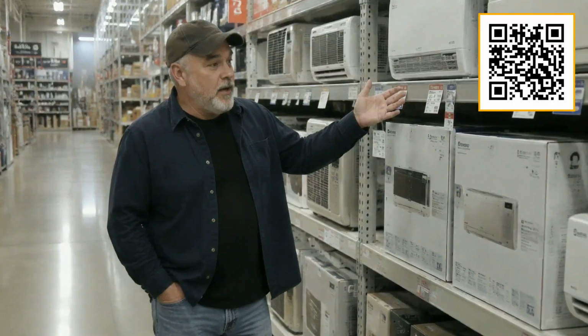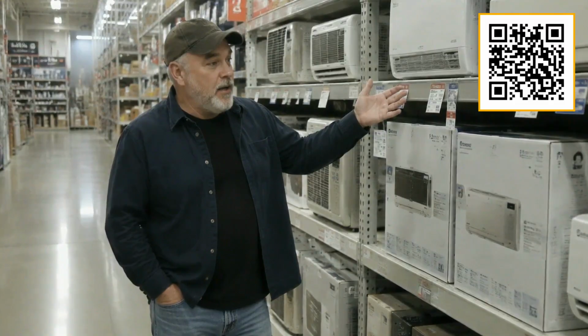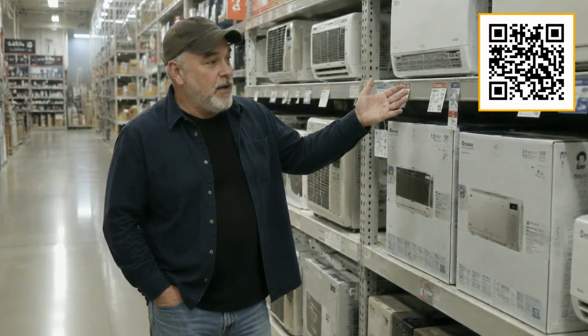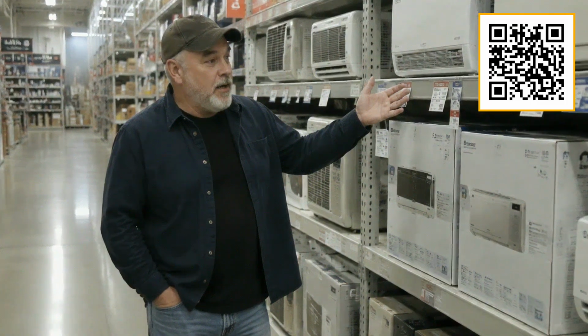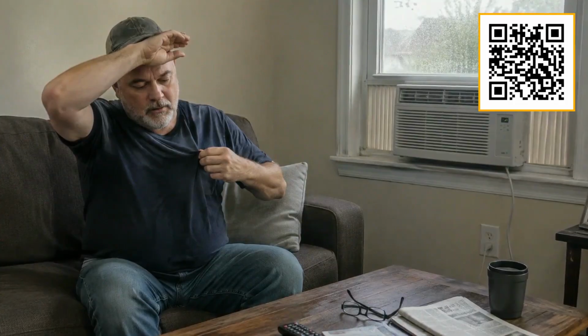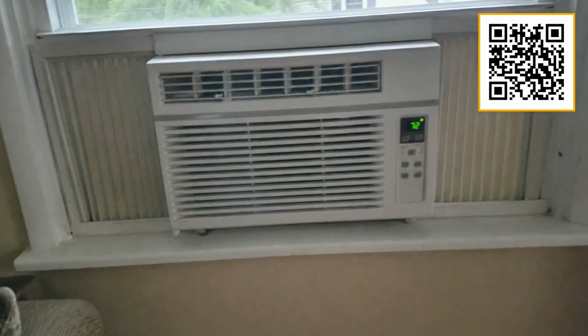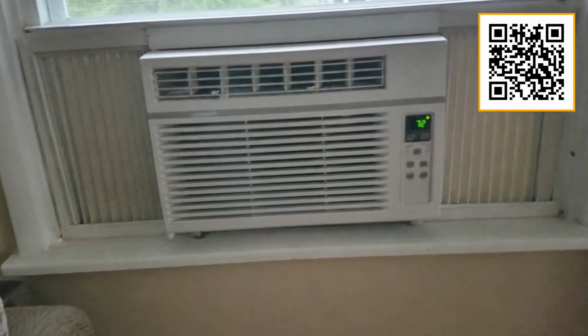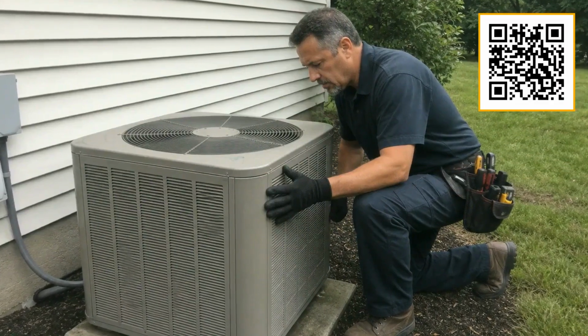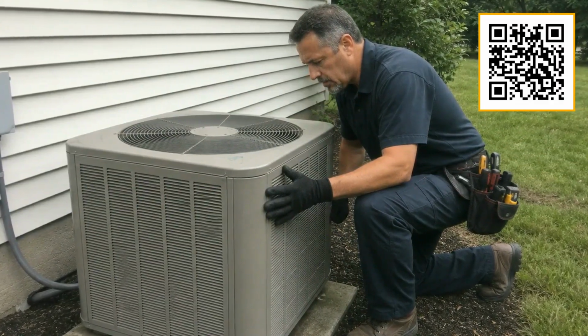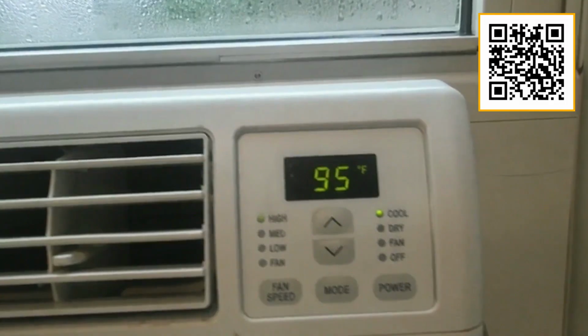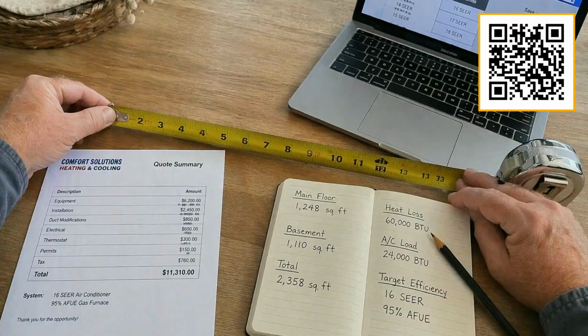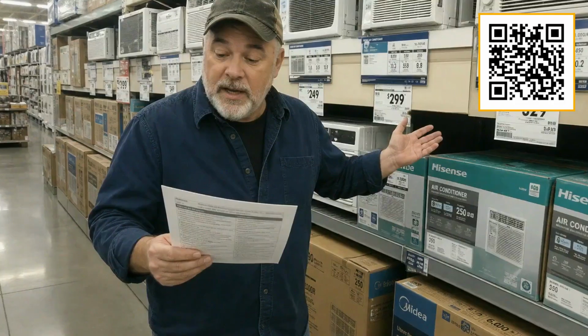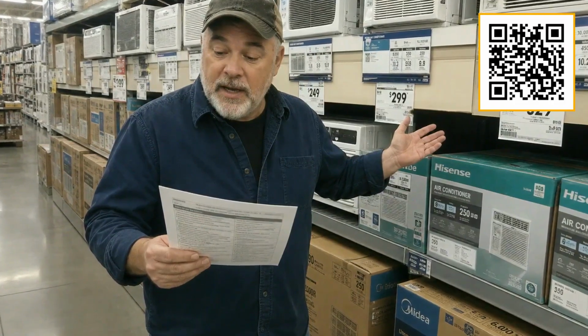Now let us talk about sizing, because this is the single most common and most costly mistake I see. Bigger is not better with air conditioning. It genuinely is not. An oversized unit cools the air so fast that it shuts off before it has had time to remove the humidity from the space. You end up with a room that feels cold but clammy, and a unit that cycles on and off constantly, which is hard on the compressor and shortens the life of the equipment. An undersized unit, on the other hand, runs constantly and never quite gets ahead of the heat. The right size is the right size.